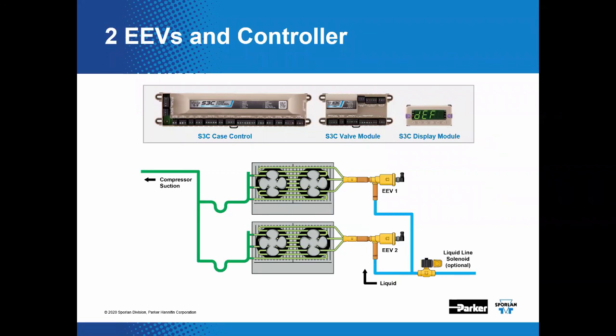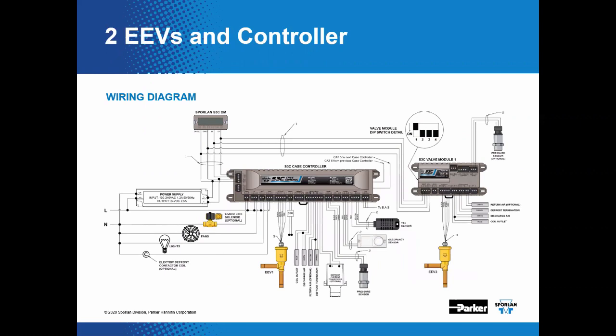Typically, coil out temperature sensors would be installed on each evaporator coil outlet with one pressure transducer on the common suction. But I kind of like the idea of having two pressure transducers, as we show here in this wiring diagram for this particular example. Again, the valve module simply extends the input and output capabilities of the single case controller. And likewise, EEV2 is connected to the valve module, and EEV1 and all the sensors and related devices are connected to the case controller. And we have included that second pressure transducer right here.